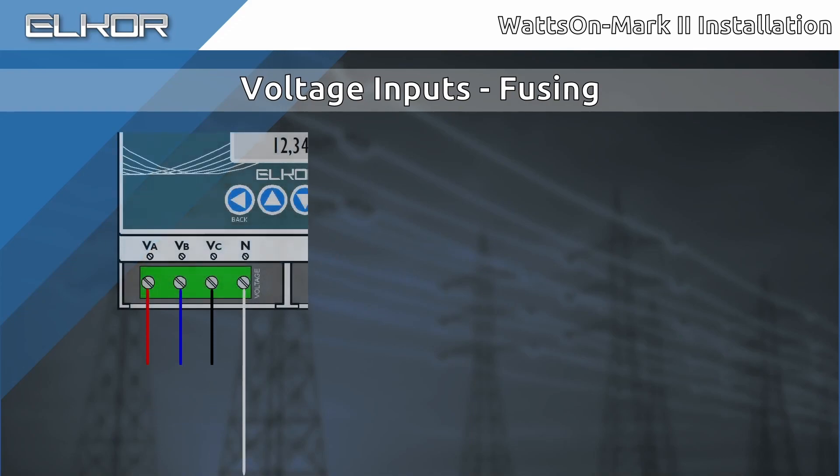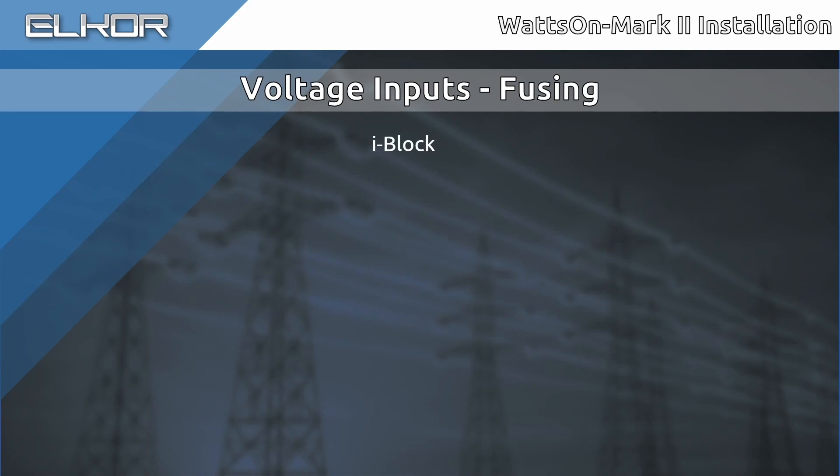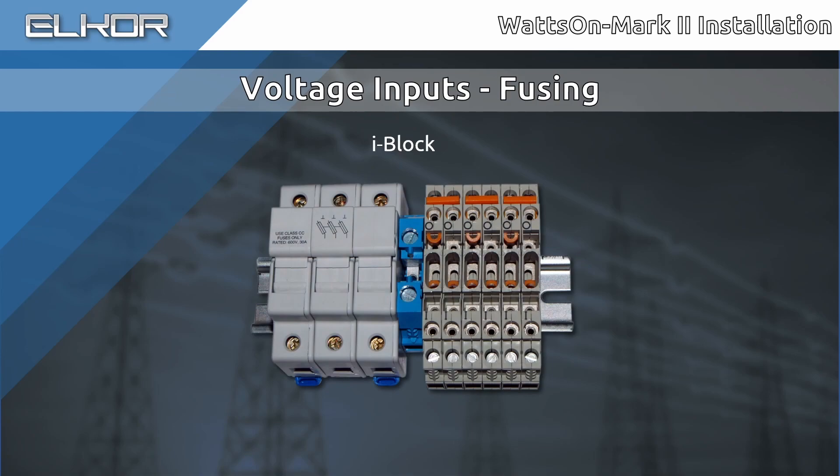The voltage inputs should be fused to protect the building wiring. Since the voltage inputs do not draw any appreciable current — less than about half a milliamp — the fuse or breaker should be the lowest value that is practical. Generally, if using an existing breaker, a 10-amp or 15-amp breaker is more than sufficient. If using fuses, ensure the correct fuse rating and specify the lowest value which is practical to obtain. Generally, 1-amp fuses are available. Elkor sells an interfacing block called i-Block, which simplifies installation. This product includes a ganged 3-position, 600-volt rated class CC fuse block, fuses, a neutral terminal, and a CT shorting interface.